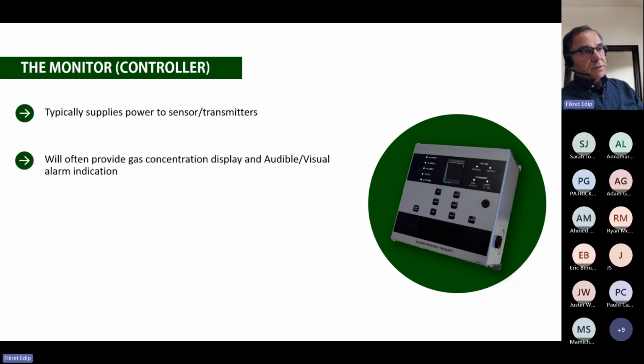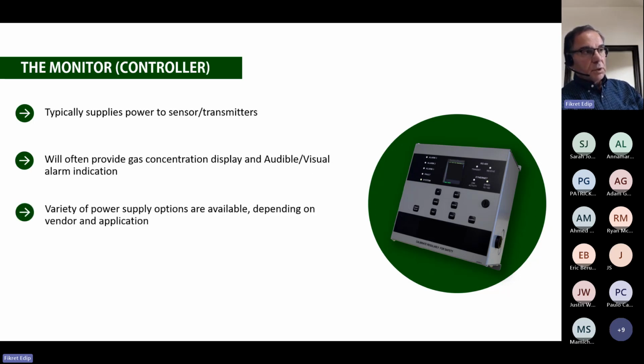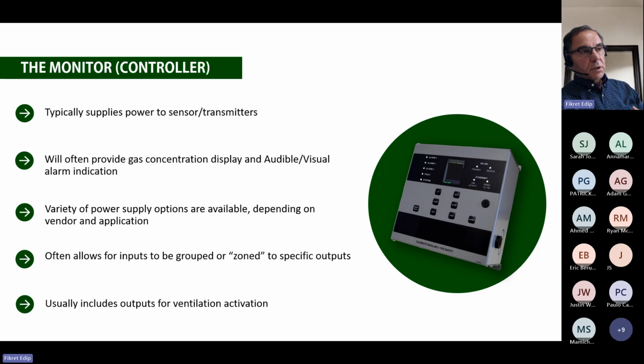The monitor, as I said earlier, is the central, or they call it head end. In the industry, we use this terminology a lot. We call it head end. That's where the controller receives signal from a transmitter and then looks at its own sequence of operation programmed by a programmer. Then it executes a certain thing, such as strobe horn or dampers, transfer fans, exhaust fans, makeup air units, or even sending a signal to a fire department or fire panel.